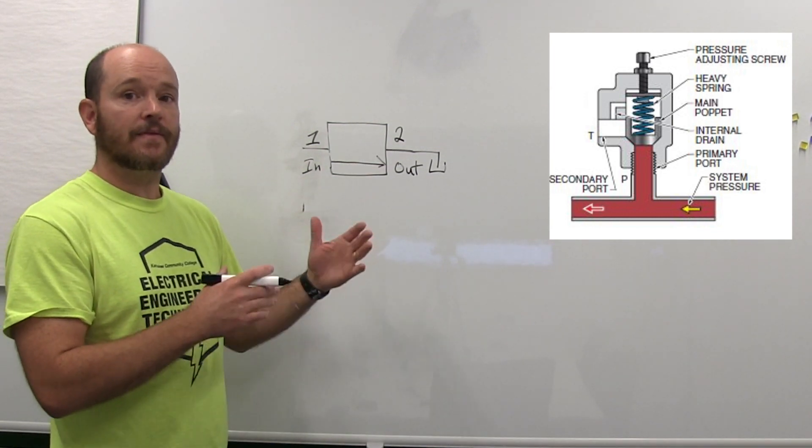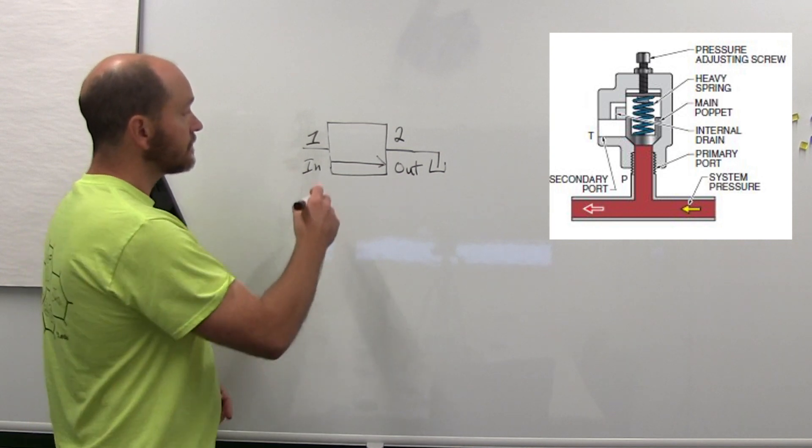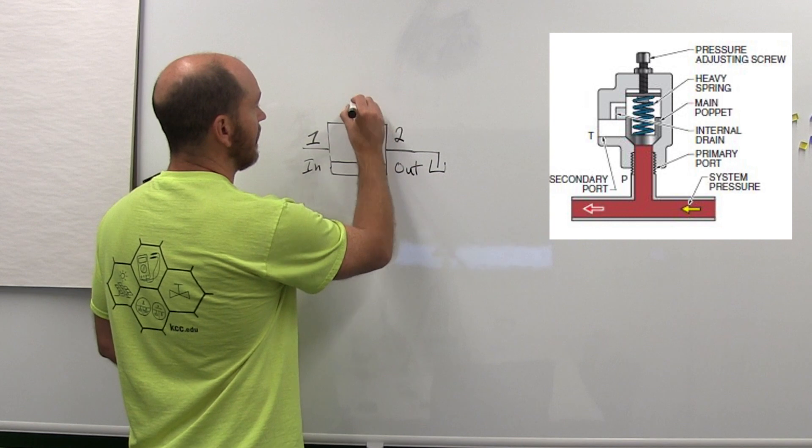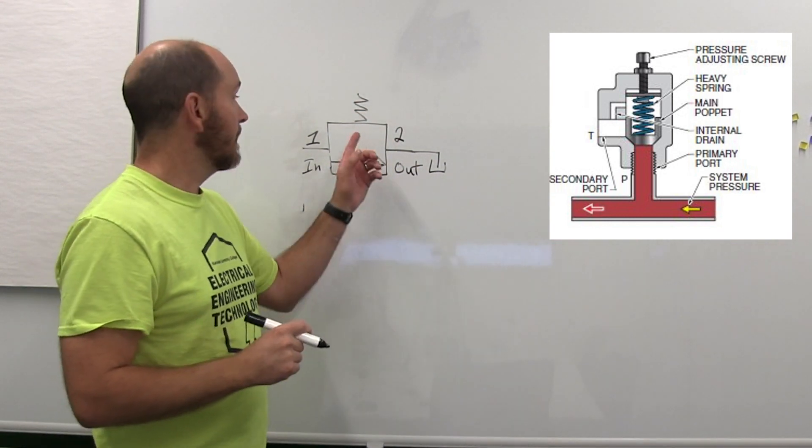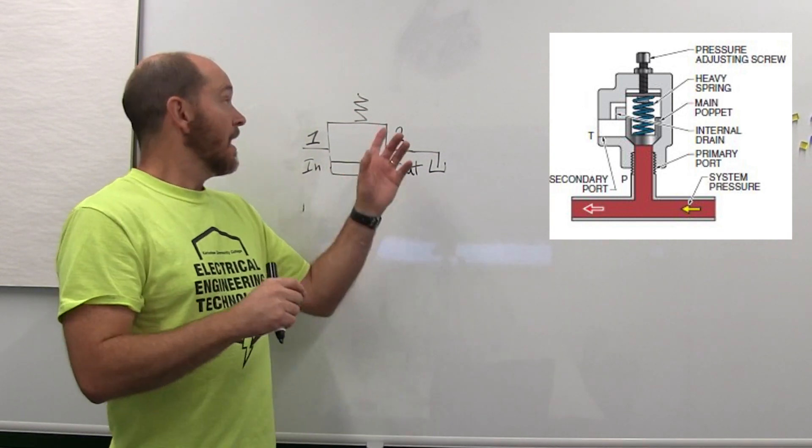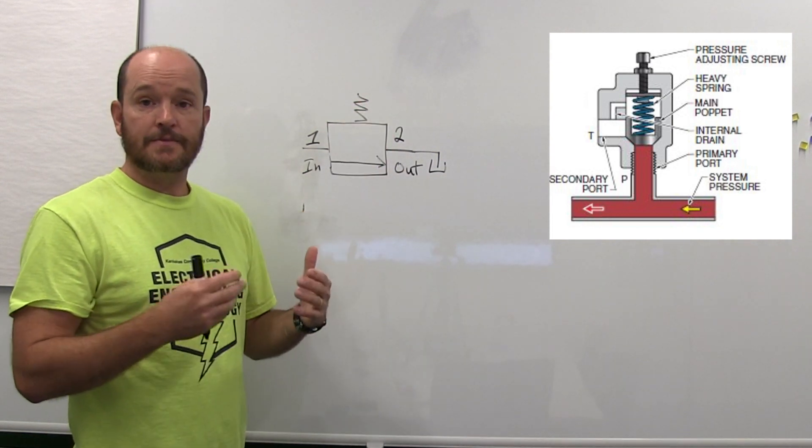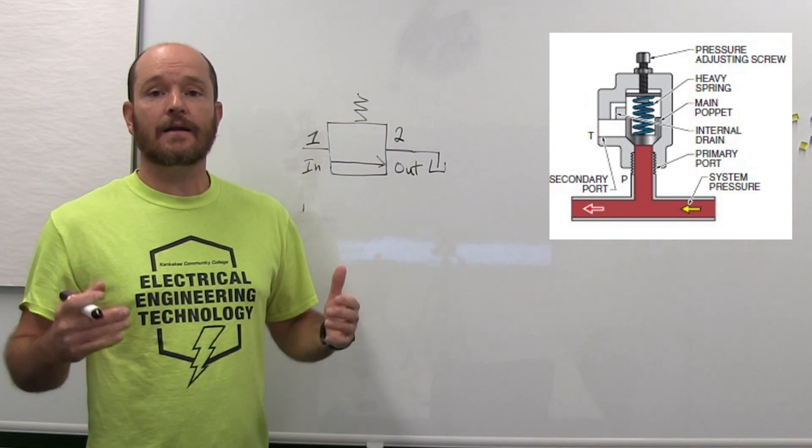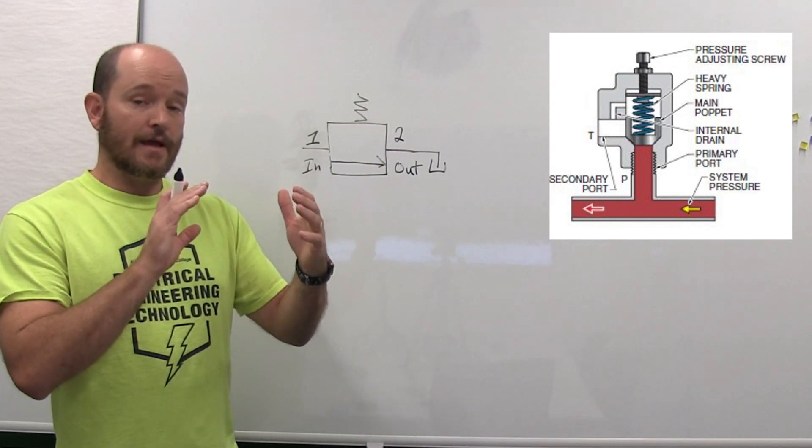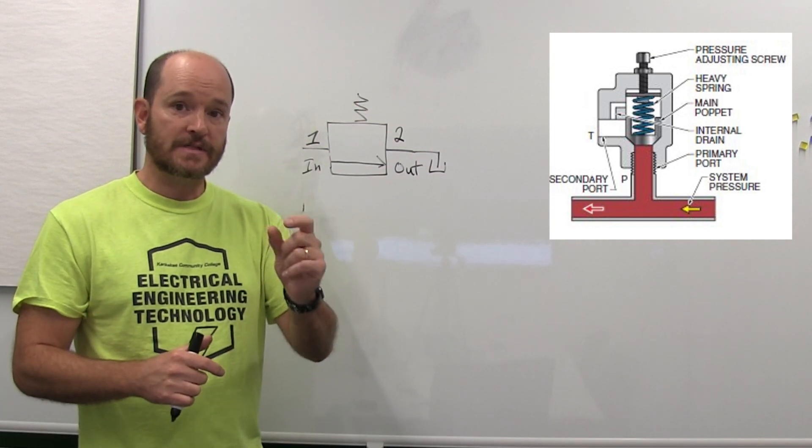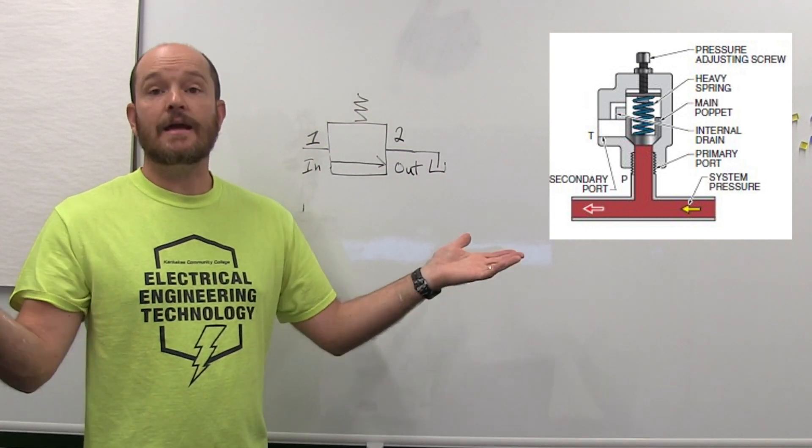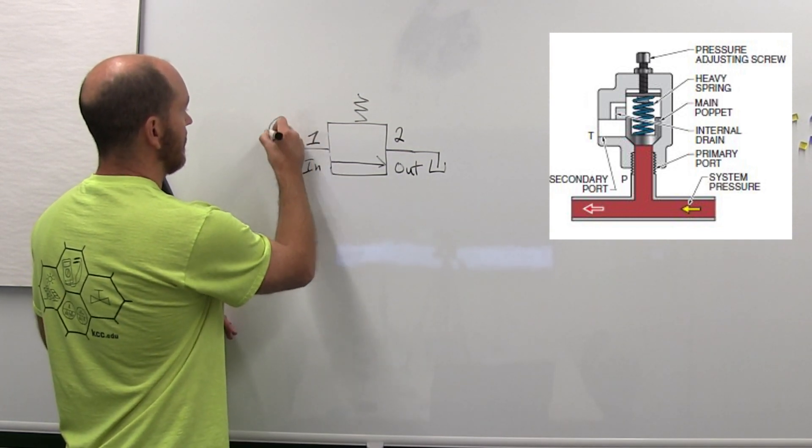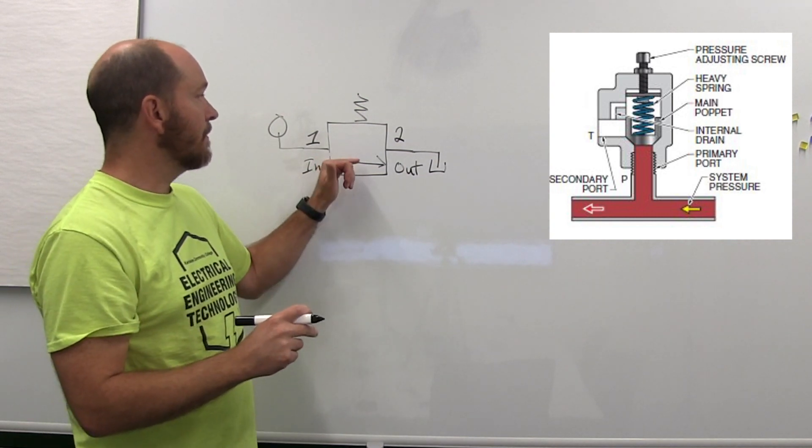The biasing spring is located on the top here. Sometimes there will be an arrow through it, sometimes there won't be. If there is not an arrow through it that means it is not adjustable—you've purchased it to open at a very specific pressure, let's just say 800 psi for example.